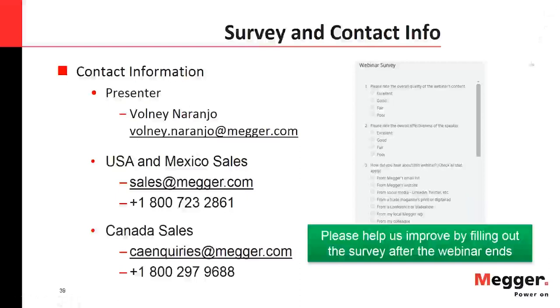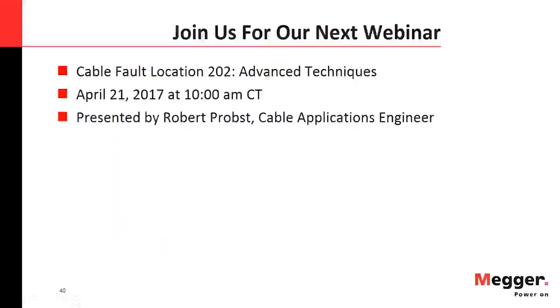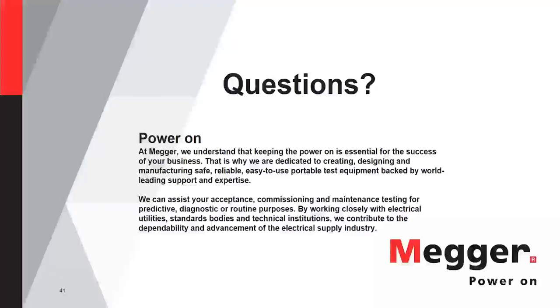their question was, we have an 18-year-old flooded lead acid battery bank. It is on an auto-alarming and monitored system on intentional grounds. We have performed and documented monthly, quarterly, and annual maintenance and testing since new, as well as performed battery cell ohmic impedance testing using a Bite 2P. All tests indicate normal and passing conditions. The question is, do we have to perform battery discharge capacity testing?